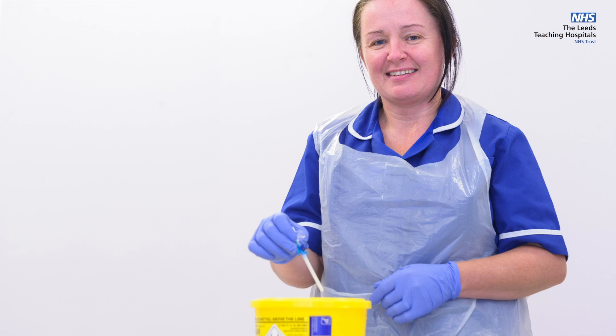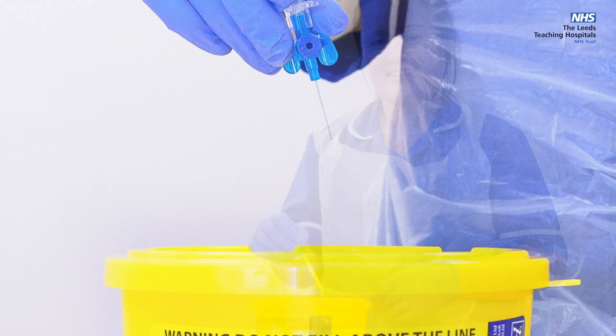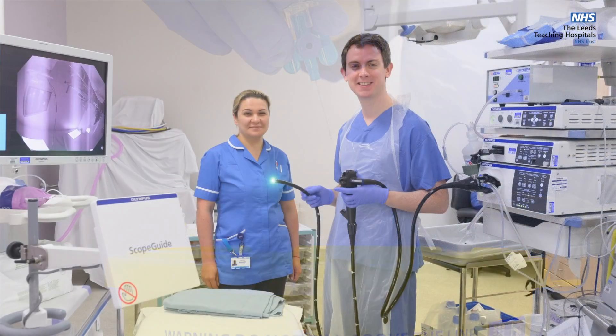to ensure that the endoscope is fully sterilized prior to any procedure. All other equipment is disposed of after a single use. At Leeds, teaching and research are an important part of our work.